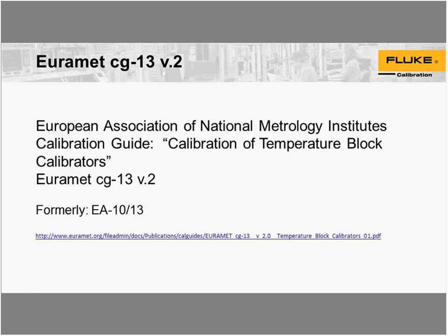A few years ago, a guideline from EURAMET was published called EA 10/13. It's currently CG13, and it describes a methodology of testing these various uncertainties and how to evaluate your temperature calibrators. So we'll basically follow along that general concept.